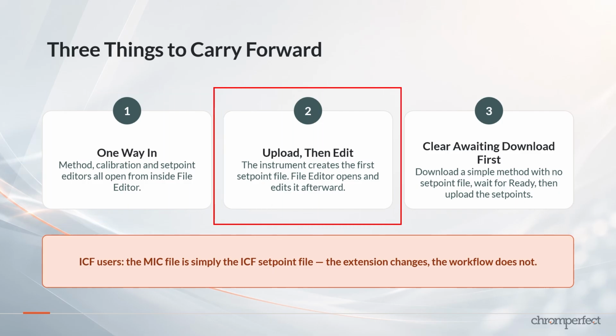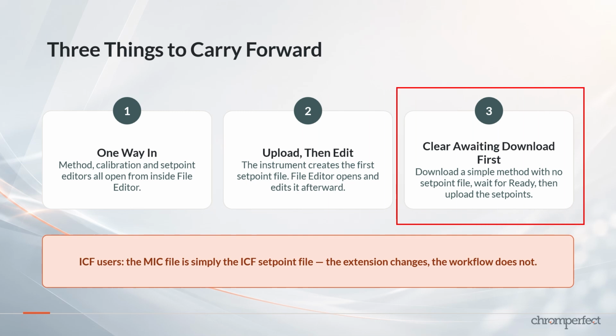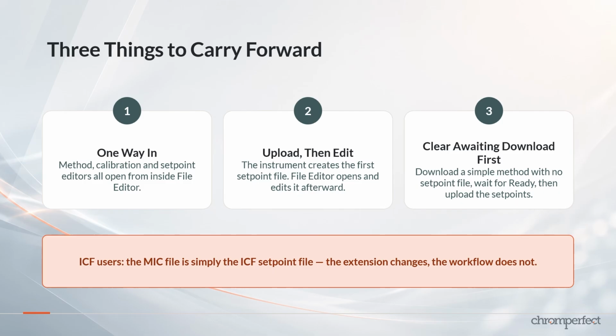Second, setpoint files are normally uploaded from the connected instrument before they are edited. They are not normally created as new blank files in File Editor. Third, if the instrument is showing awaiting download, first download a simple method without a setpoint file attached so the instrument reaches ready. After that, upload the setpoints and continue with editing.